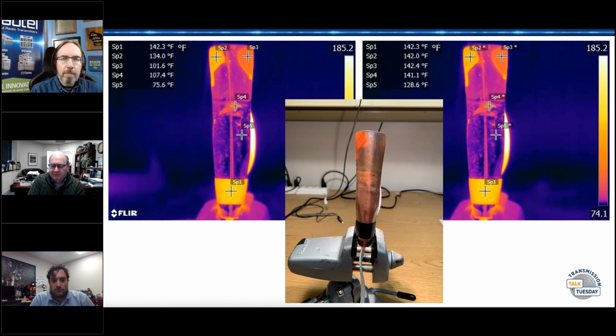You've got to account for emissivity, which Rafael's talking about, reflections, wind, humidity — there's a lot of stuff that goes into it. For 90% of what people are doing at transmitter sites and in most places in an industrial plant, you don't need to come up with an exact number unless you really have an insurance reason for it, or you want to track something over time. So what you're looking at is more like, this is a whole lot hotter than everything else, or a lot hotter than it was last month.